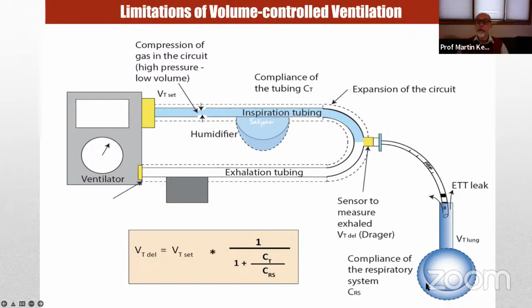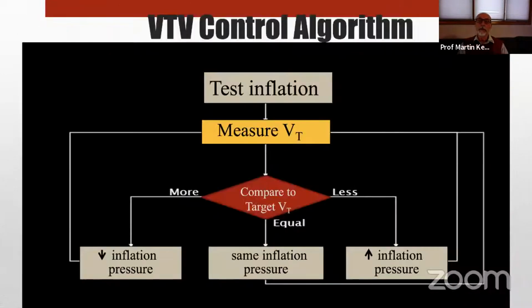But when you have a tiny baby attached here and when you have an uncuffed endotracheal tube, there's a lot of loss of volume to compression of gas within the circuit, leak around the endotracheal tube, so that you may have to set a tidal volume of 10 or 12 ml in order to achieve an effective tidal volume entering the lungs of around 4 ml. This, of course, is variable. It's not a constant relationship. And leakage is, of course, also highly variable. So this did not work very well. And that was the main reason why we all reverted to pressure controlled ventilation.